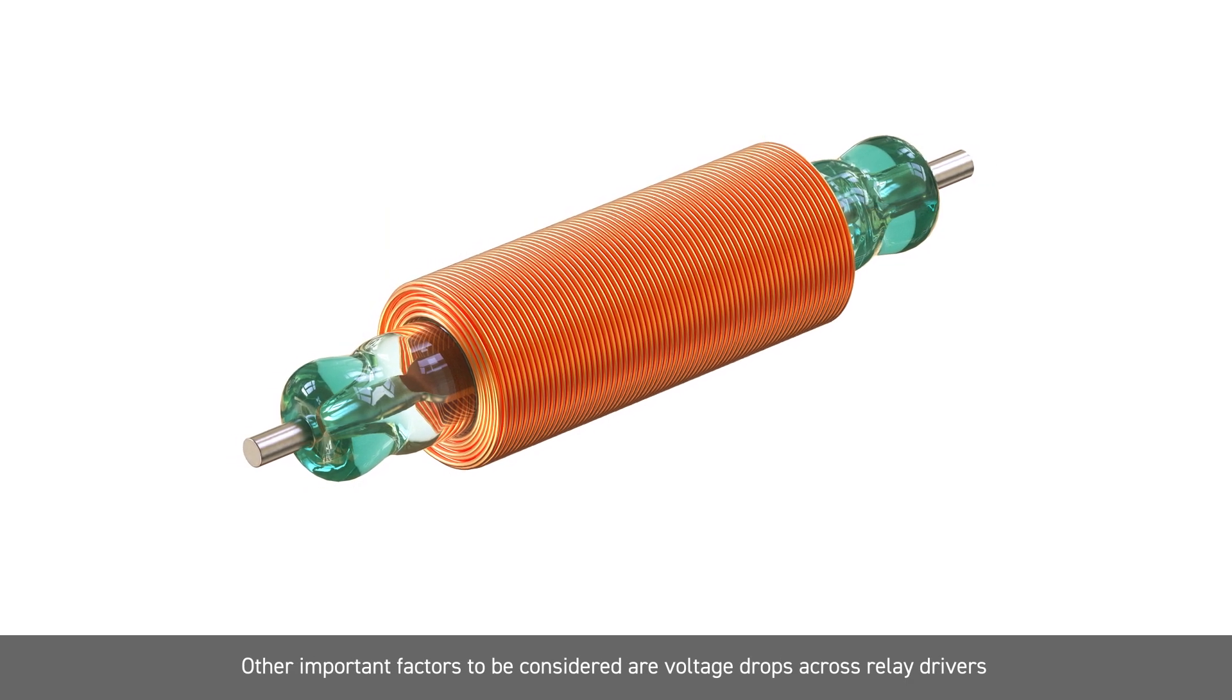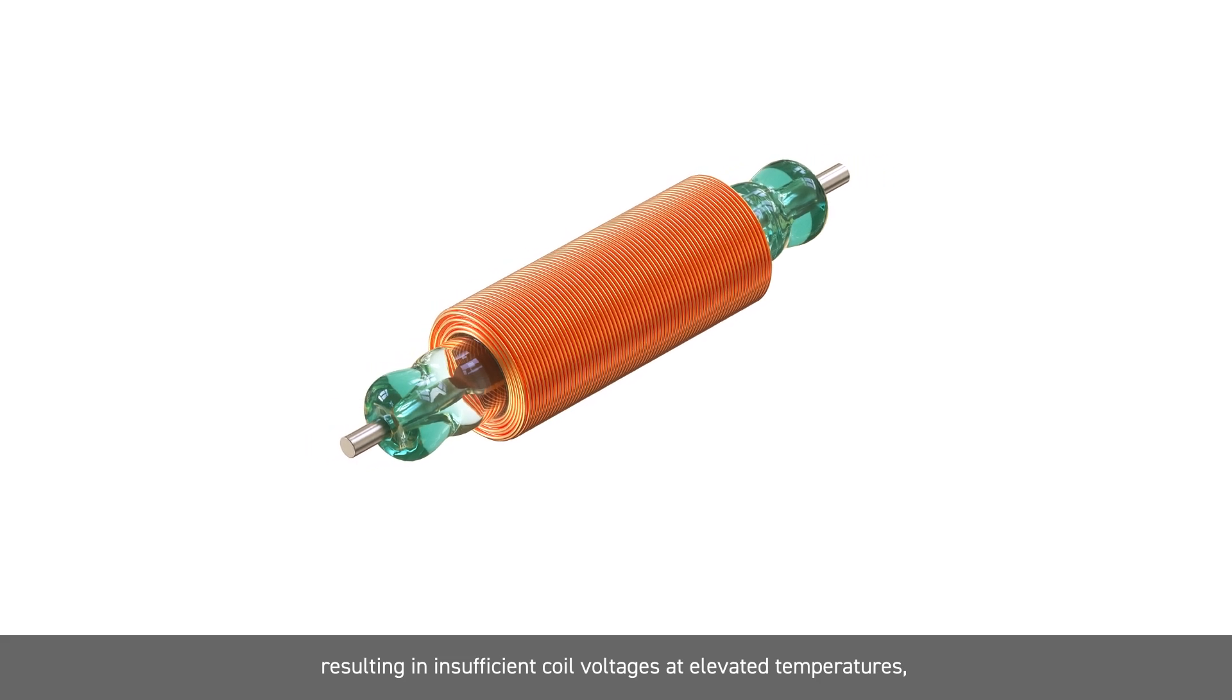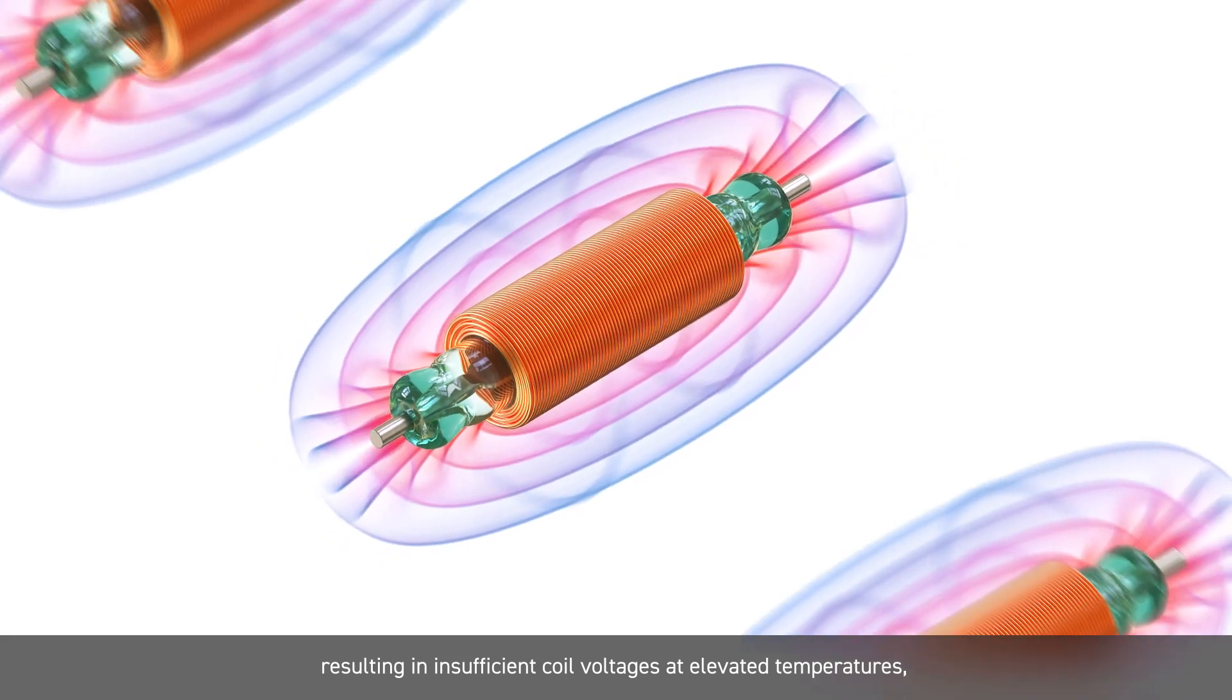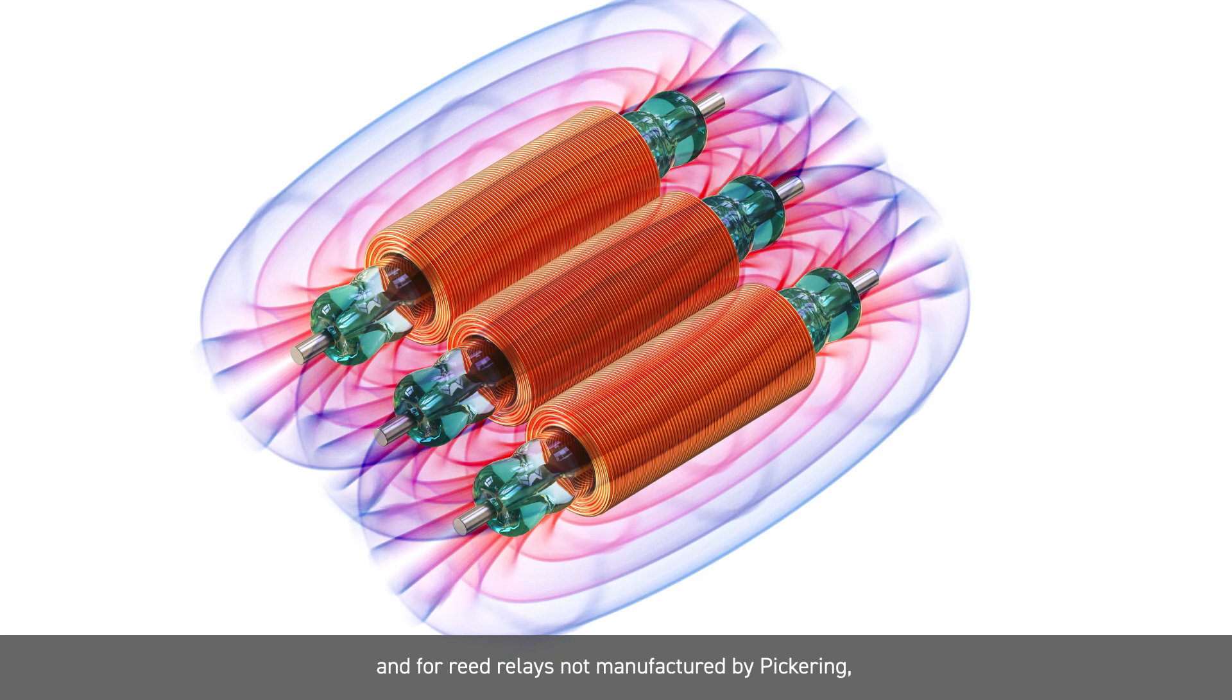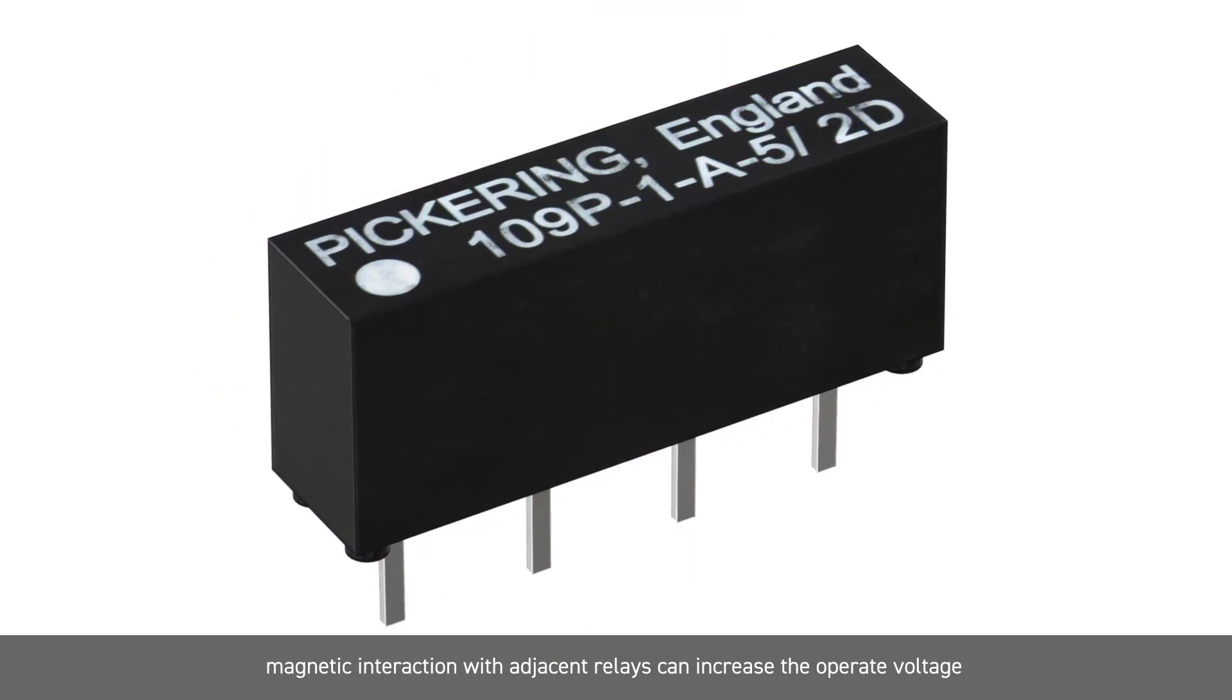Other important factors to be considered are voltage drops across the relay drivers, resulting in insufficient coil voltages at elevated temperatures, and for reed relays not manufactured by Pickering, magnetic interaction with adjacent relays can increase the operate voltage.